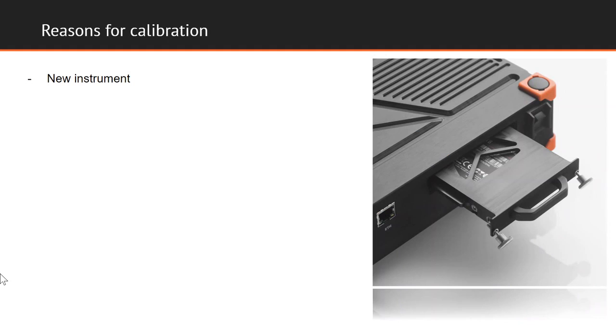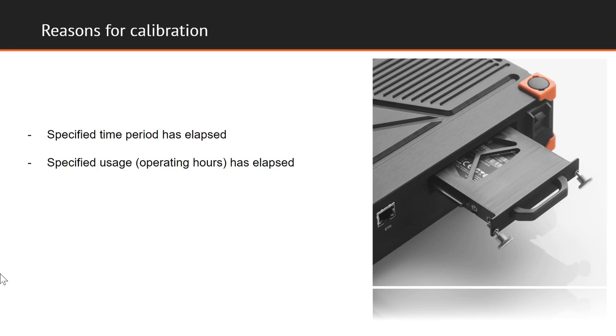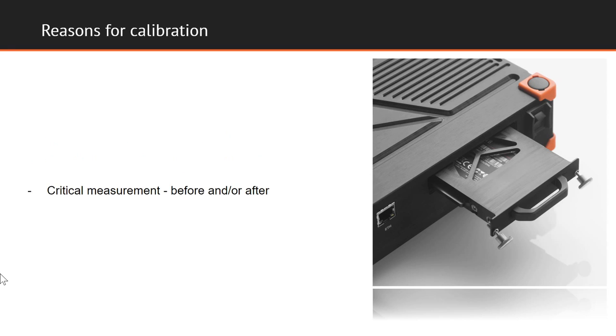Generally speaking, calibration should be performed in the following situations. Whenever we acquire a new instrument that has not been utilized before, after any kind of repair or modification has been carried out on the measurement equipment, in the event of specified time period or specified usage in operating hours having elapsed. It's also a good idea to carry out calibration before and after a critical measurement, just to ensure that characteristics of the system remain the same during the measurement process.